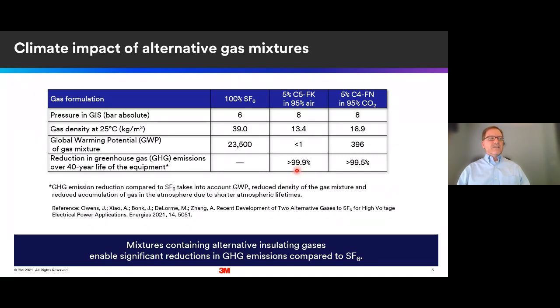The insulating gas itself has greater than a 99.9% reduction in greenhouse gas emissions compared to SF6. In the case of the C4 nitrile, it's nearly that high, even though the GWP is not less than 1. Over the 40-year operating life of a piece of equipment, for example, it would reduce the greenhouse gas emissions by 99.5%. And in fact, if you carried out that calculation over the 100-year time horizon that is used to calculate the GWP, it too would show a greater than 99.9% reduction in greenhouse gas emissions when compared to SF6.